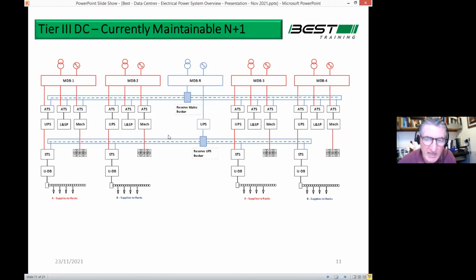But to make that work on the UPS, we end up having to have a reserve UPS distribution system as well. So the top blue line there represents the power distribution system for mains power, and the bottom blue one coming down this way represents the UPS reserve power system. And you'll see now they go through a similar switch, but in this case, it's not an ATS, it's called an STS, which means static transfer switch. So it's static, it changes over to an electronic transfer system, where the transfer from one to the other is in the order of milliseconds, maybe 3 or 4 milliseconds. Whereas with an ATS, it could be 20 or 30 milliseconds. You couldn't have that with critical load. It would see it as an outage and your servers would crash. So that's why, if you're doing this arrangement, and this is not the only one, there's hundreds of different ways, this is just one example I'm giving.